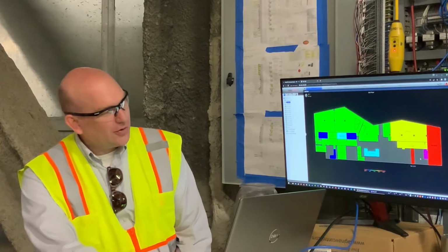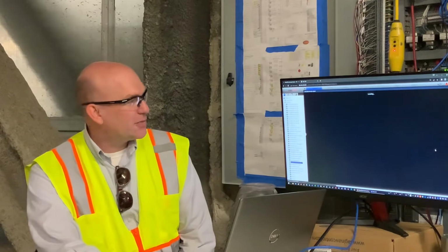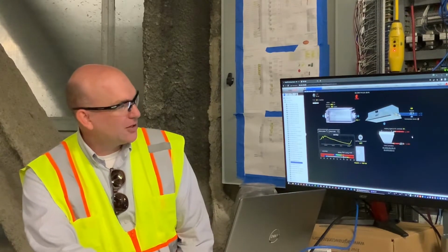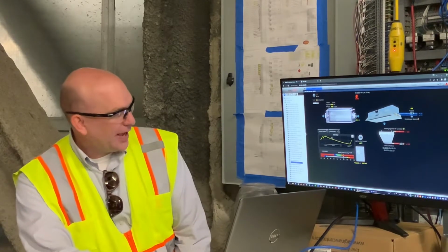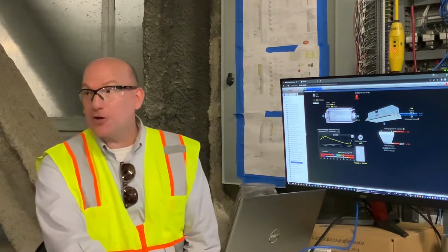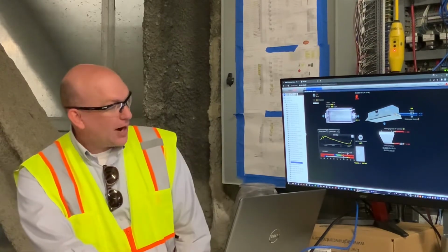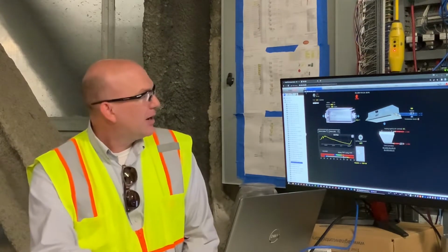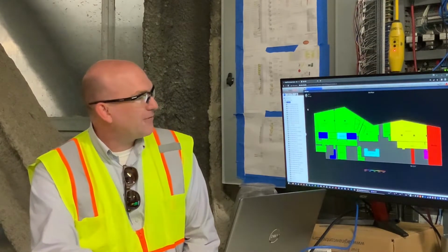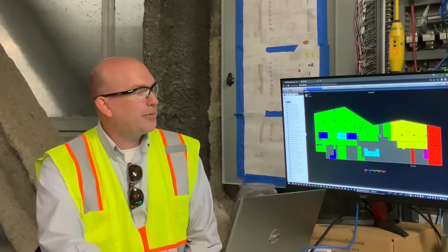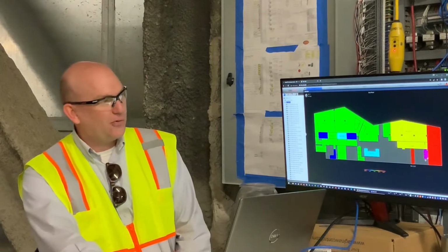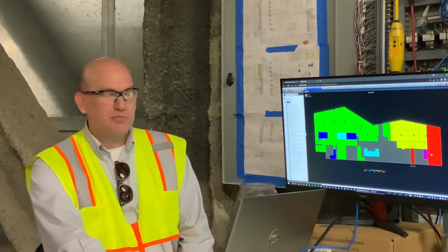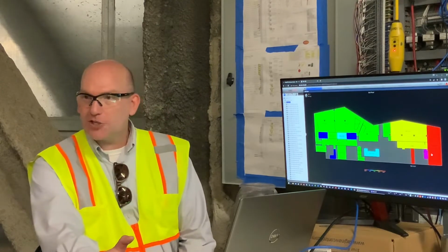And then if we look over here, we got a couple in red, which tells me that they're most likely in alarm. So in this case, we have our zone temperature 80 degrees in that room. Our set point 75. That's why it's red. It's a little hot in there today. So I'll preface this by saying that we're probably going to see some alarms today on floor plans because you guys are working in rooms. There's still construction going on in certain areas.